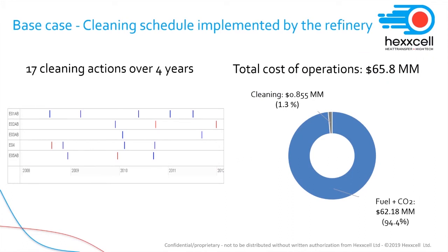This is a very simple heuristic that led to performing 17 cleaning actions over 4 years of operations, for a total operating cost of $66 million, with the cost of cleaning representing 1.3% of the total costs, and the rest being fuel consumed in the furnace and costs associated with CO2 emissions. As you can see from the cleaning schedule implemented by the refinery, they were using both mechanical cleaning in blue and chemical cleaning in red. In some cases, the chemical cleanings were not effective. For example, in E04, they had to perform a mechanical cleaning action only a few months after they cleaned chemically. In other cases, chemical cleanings were actually quite successful. So clearly selecting the right type of cleaning depending on the status of the heat exchanger is very important.